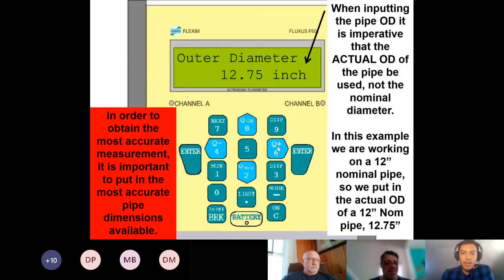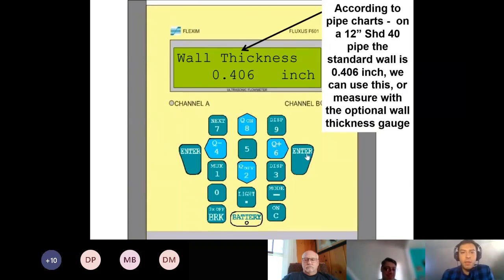So for this example, we're going to start with 12.75. Wall thickness also in the lookup chart. For this it is going to be 0.406. This is a 12-inch schedule 40 pipe. We can also use an ultrasonic thickness gauge to measure the wall thickness if you want it to be a little bit more accurate.